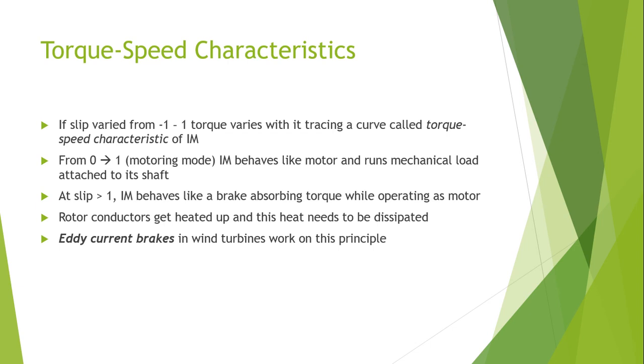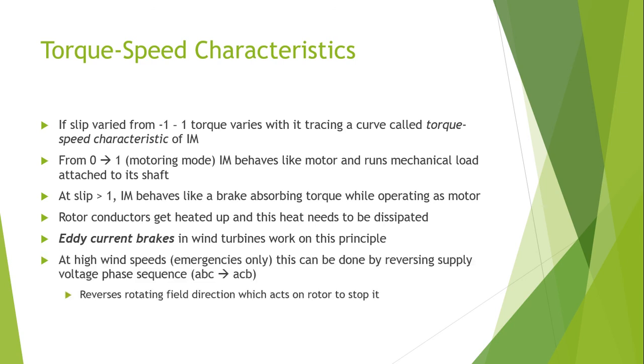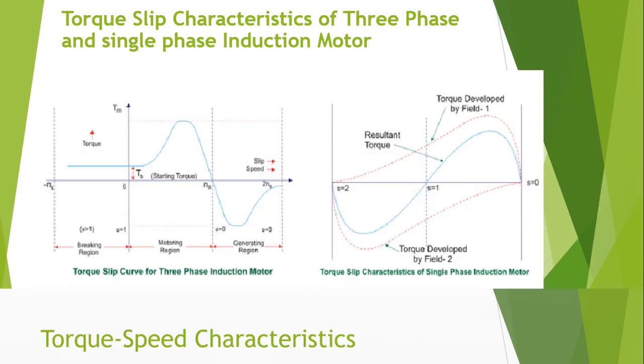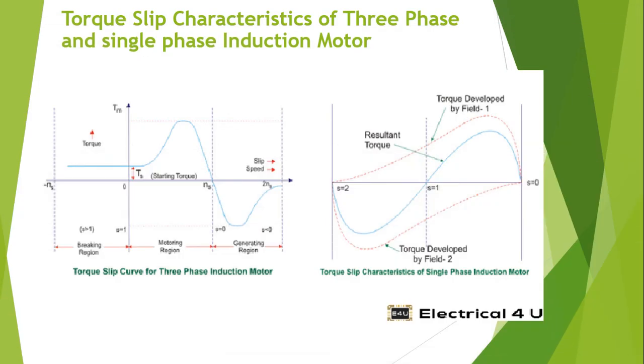Smaller machines are air-cooled and larger machines employ water cooling systems. There are also eddy current brakes; wind turbines work on these principles. At high wind speed, braking can be done by reversing the supply voltage phase sequence — for example, changing from A-B-C to A-C-B — which reverses the rotating field direction, acting on the rotor and helping to stop it.